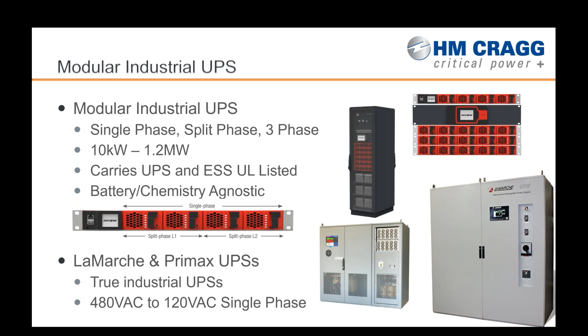Beyond that, Lamarche and Primax UPSs — this is the very unique industrial UPS sale, kind of those Amatech type projects where it's true industrial UPSs, and the telltale sign of that is a 480 volt 3-phase input with a 120 volt single phase output. These are all transformer based. They're going to have dedicated inverters, dedicated chargers, and be that truly robust 30-year UPS design.